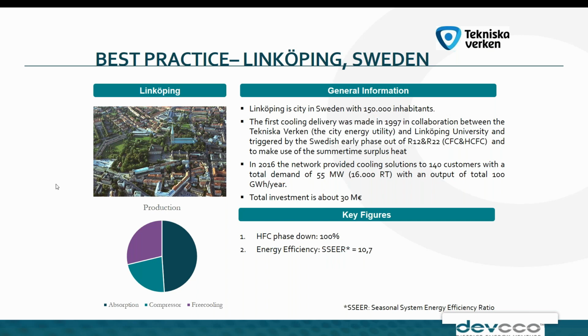We can also see that in this case it's a mix between free cooling, which is more than 25% in this case, absorption, and compressor cooling. That brings it up to a seasonal system efficiency of over 10. I think they're actually up to 12.5 now, the latest I heard. So compared to 2.5, which is the average from the measurements done, we can see it is at least 5 times more efficient.